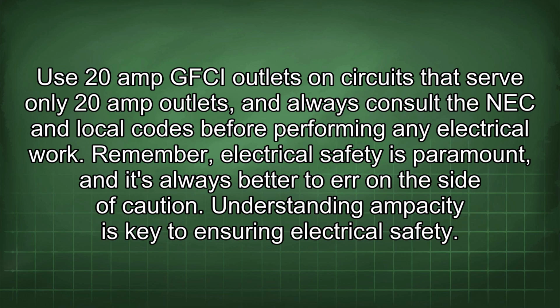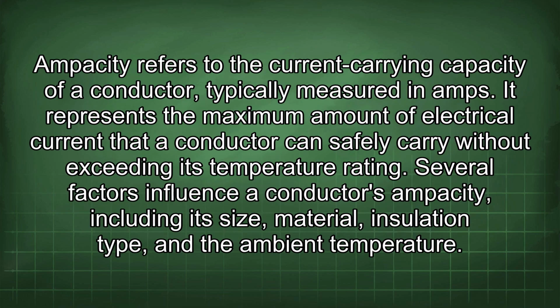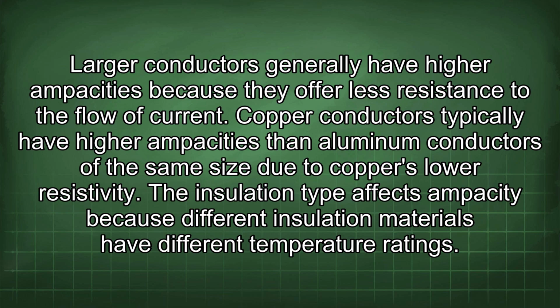Understanding ampacity is key to ensuring electrical safety. Ampacity refers to the current carrying capacity of a conductor, typically measured in amps. It represents the maximum amount of electrical current that a conductor can safely carry without exceeding its temperature rating. Several factors influence a conductor's ampacity, including its size, material, insulation type, and the ambient temperature. Larger conductors generally have higher ampacities because they offer less resistance to the flow of current. Copper conductors typically have higher ampacities than aluminum conductors of the same size due to copper's lower resistivity.